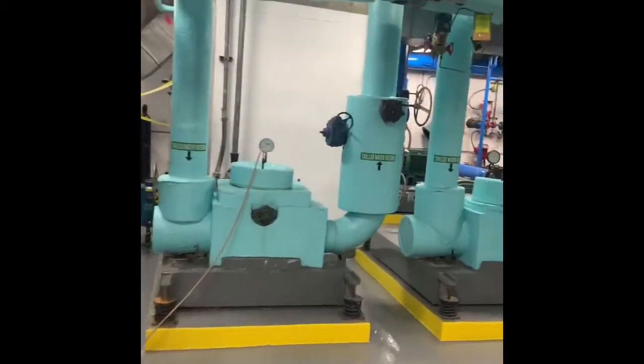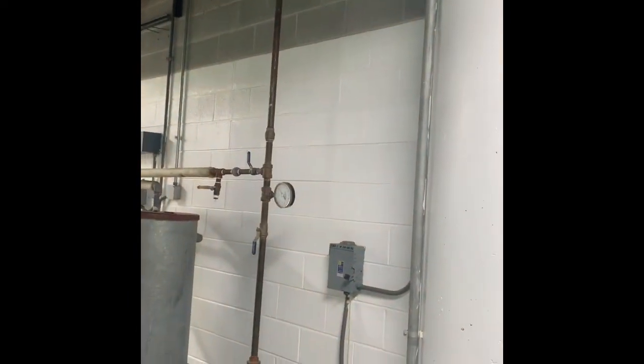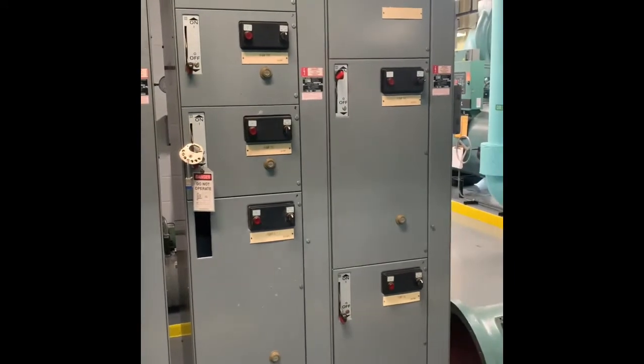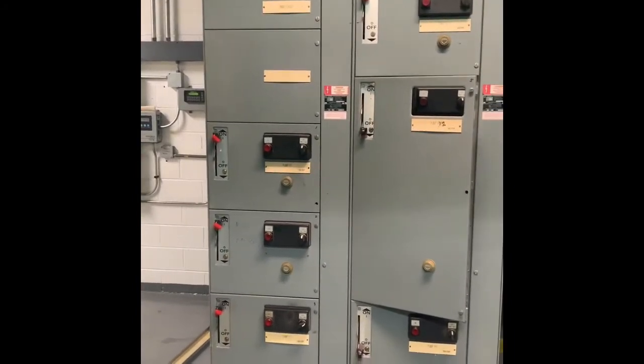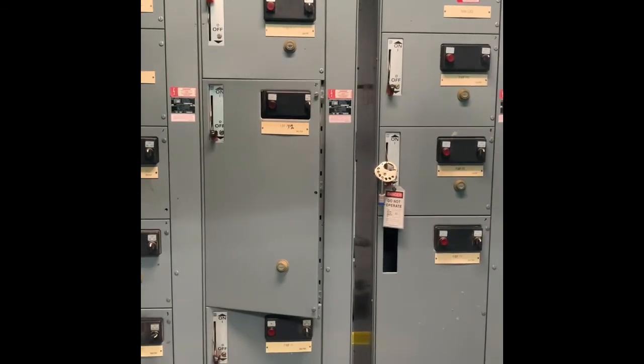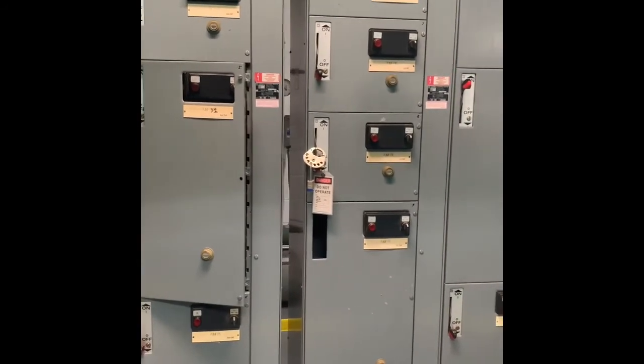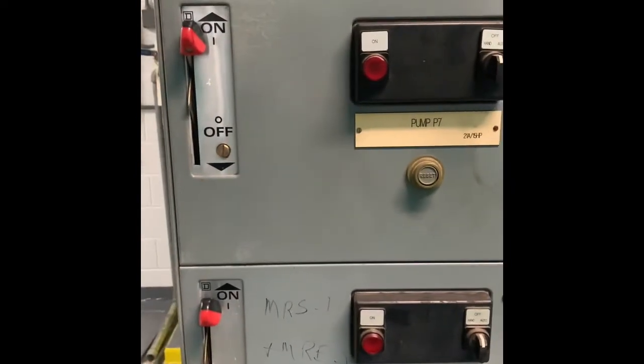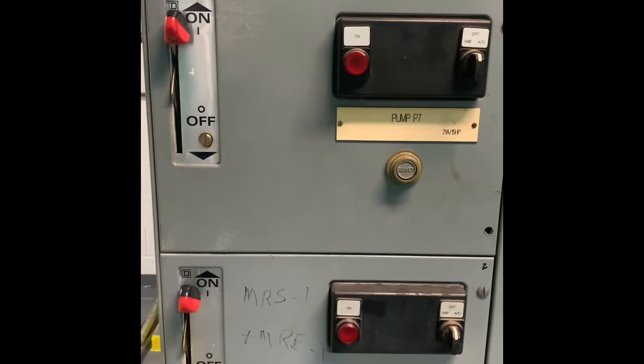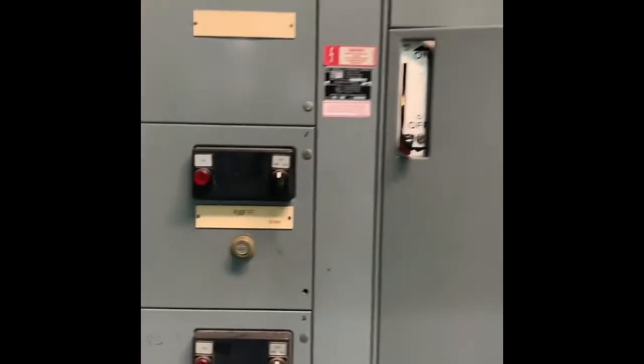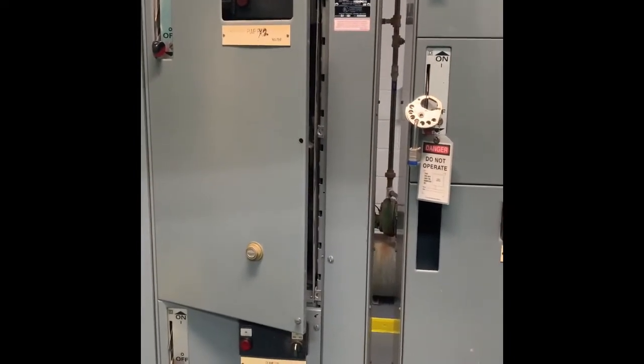All right, but back on the theme of electrical distribution, on the other side of this wall is a switchgear room. From that switchgear room comes power to this MCC, this motor control center. Motors are, of course, the most common loads requiring simple and complex control. And an MCC combines individual control units into standard modules that make it really easy for troubleshooting and servicing motor control circuits. So you can see all these individual buckets, as I call them, or modules. They just snap right into place. There's bus bars back there, and they just snap right in there.